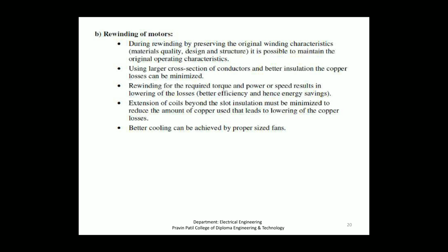New technologies are available which help reduce the losses in a rewound motor. Rare cases have shown that a motor's efficiency increases after being rewound. A common problem occurs when heat is applied to strip old windings. The insulation between laminations can be damaged, thereby increasing eddy current losses.